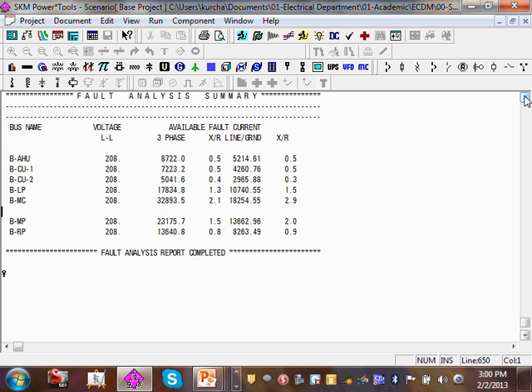The RP is receptacle panel for us. LP is lighting panel. The lighting panel is a little bit further away, so it's 17.8. MC, can you guys remember the MC? That's meter cabinet, right at the beginning. At the meter cabinet, look at the value, 32. At the meter cabinet, there's no circuit breaker. It's ahead of the main. So if you were to open this one, you have 32,000. And here's your ground fault.